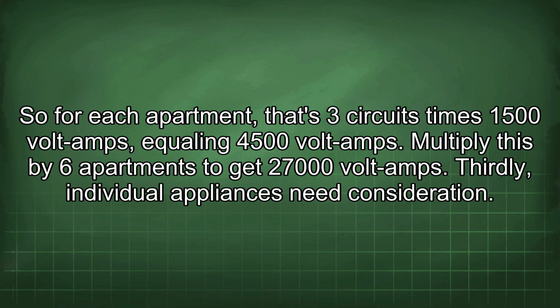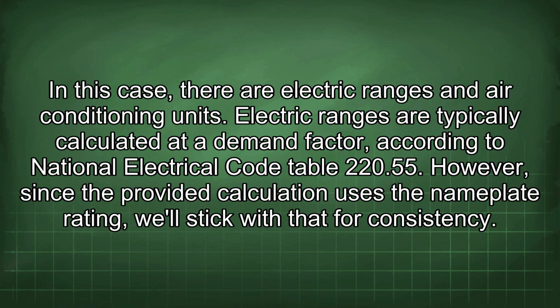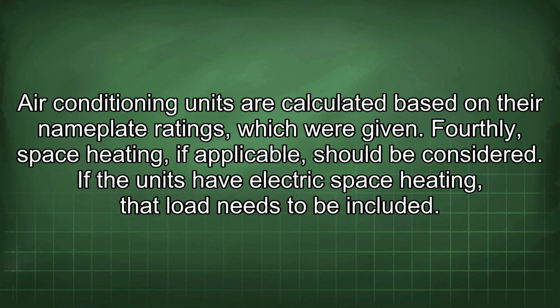Thirdly, individual appliances need consideration. In this case, there are electric ranges and air conditioning units. Electric ranges are typically calculated at a demand factor, according to National Electrical Code Table 220.55. However, since the provided calculation uses the nameplate rating, we'll stick with that for consistency. Air conditioning units are calculated based on their nameplate ratings which were given.